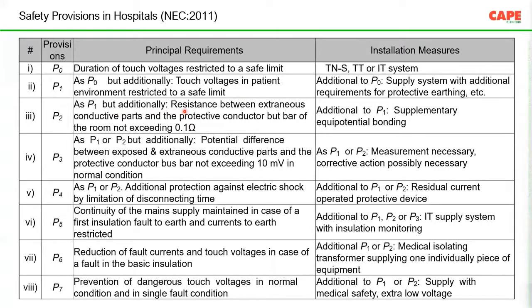P2, additionally, the touch voltage is reduced to less than 25 volt. Resistance between extraneous conductive parts and the protective bonding conductor bus bar of the room shall not exceed 0.1 ohm. Now, in the new standard, this has been modified a little bit to 0.2 ohm. But how to measure this is also equally important. If you take a multimeter and measure the continuity resistance, of course, you get erratic values. You have to have a very good, high quality micro ohm meter to make this particular measurement. Then P3, I don't want to read much into it.